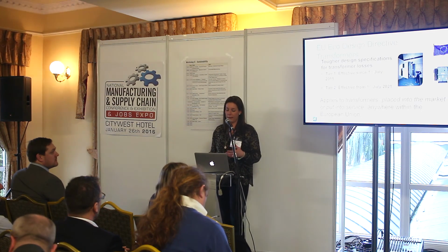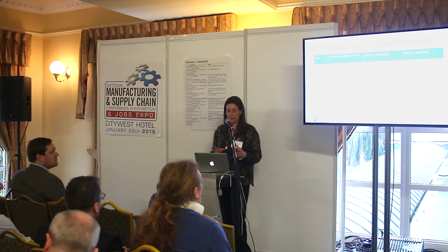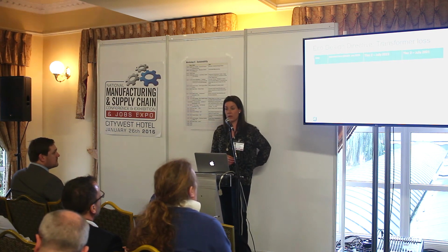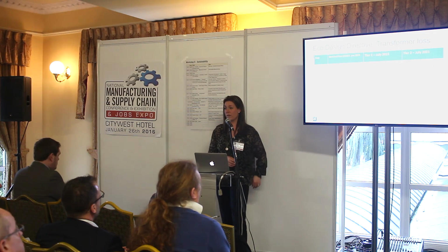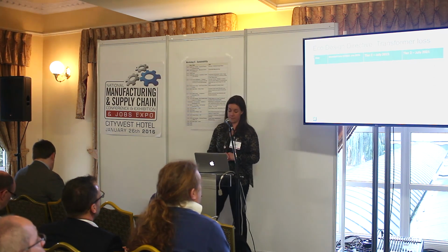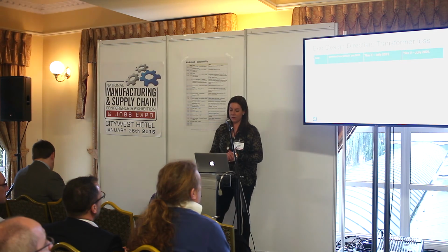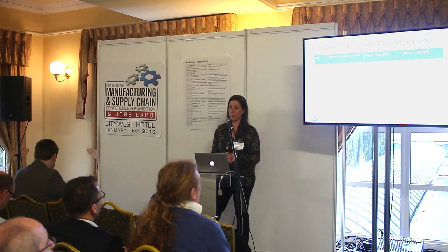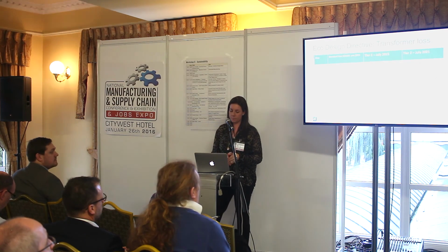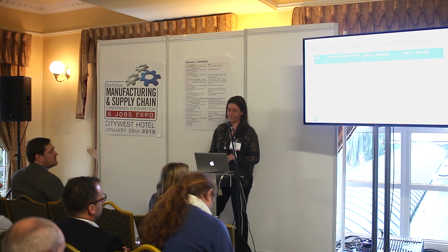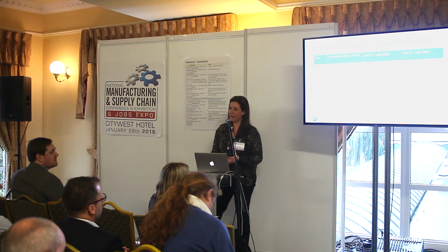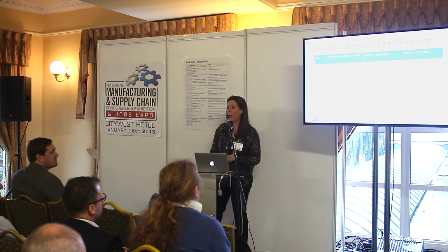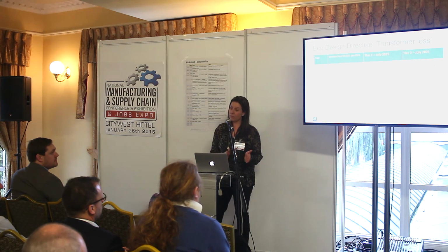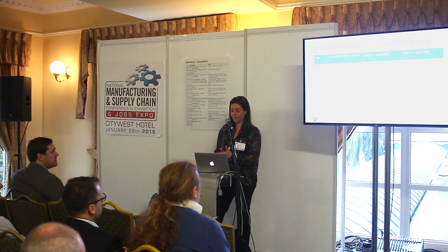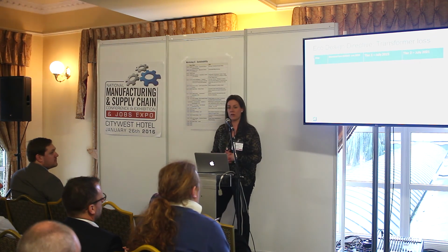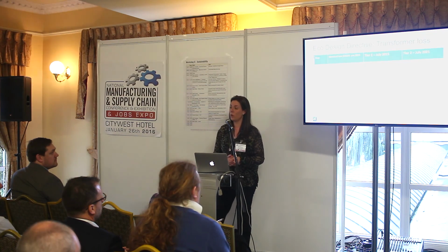Just to put it into perspective, I'll put a table here comparing - you can see there, 1,000 kVA, that's the sort of average transformer size you might have in your factory. On the left-hand side it says standard loss - we used to make transformers pre-2015 with those loss levels. Tier 1 for July 2015 asks the manufacturer to design and produce transformers that are 20% lower in losses. Then further to that, by 2021 we have to manufacture a further 26% lower losses. So it really is a massive shift in the transformer industry for all of us.